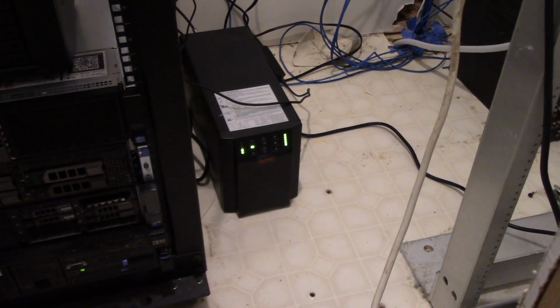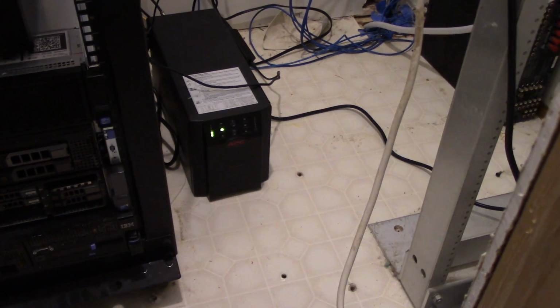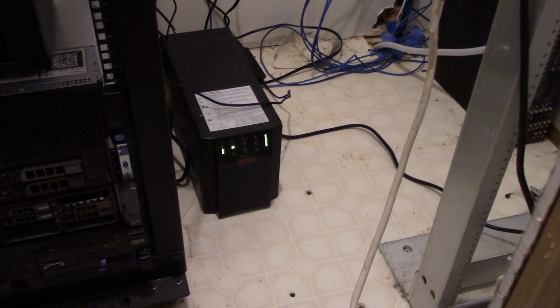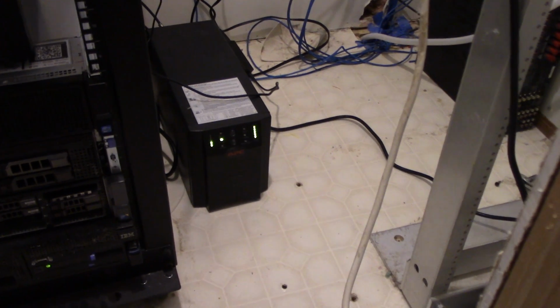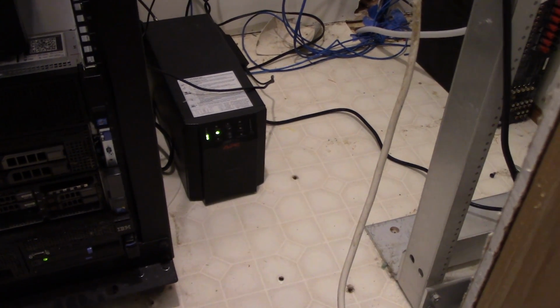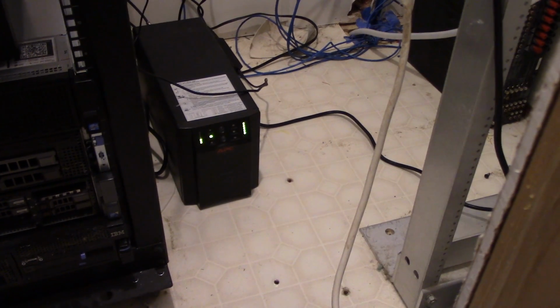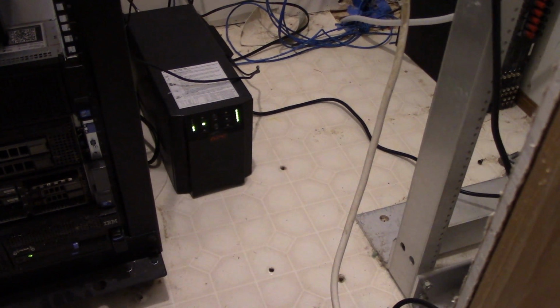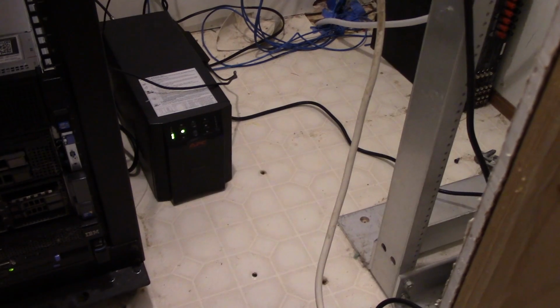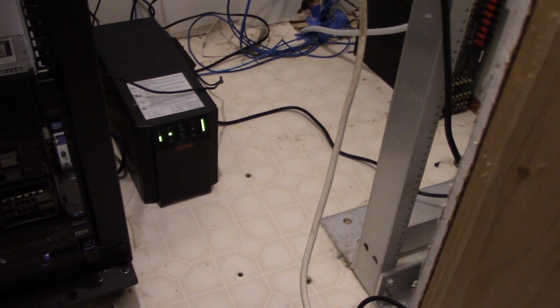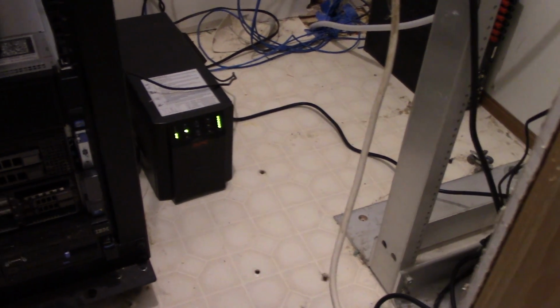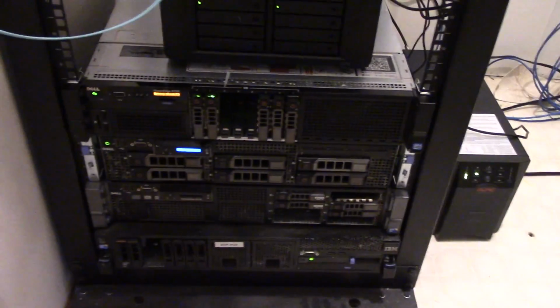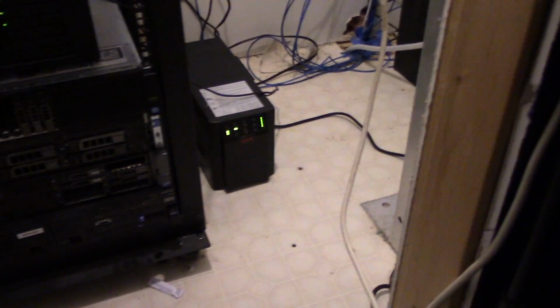That's when I looked over and noticed the UPS was still flashing. The left LED is the load, and I've only got 2 out of 5 or 6 LEDs lit. The one on the right is the battery indicator. Initially I thought I might have a fault in the UPS, but I went back and looked at the UPS logs, and it determined that it could not determine the amount of runtime on the battery, so that's why it's flashing. I still need to do a runtime calibration on the unit.